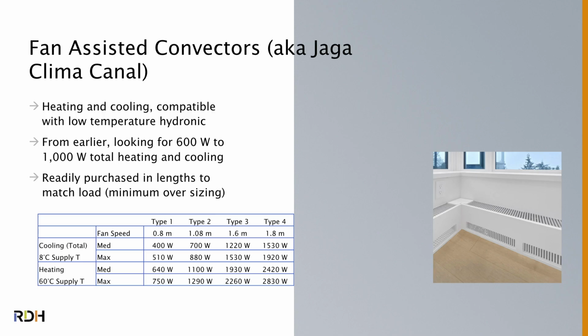I like these, and actually one of the big developers is using these, Tridel now. These are essentially fan coil convectors. They're baseboard radiators that have little fans on them, highly efficient fans. The fans don't even turn on unless they're needed, as an extra boost for heating and cooling. They can do heating and cooling.